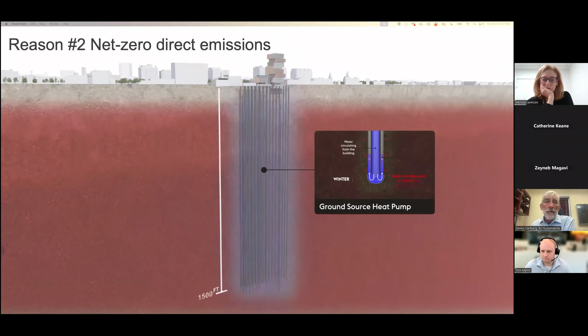The bore field has 31 closed-loop boreholes using water as the thermal transfer. These bores are connected to a plate and frame heat exchanger in the basement through 9 circuits. Water is used on the ground side of the plate and frame heat exchanger. A glycol water mix transfers the thermal energy from the other side of the plate and frame heat exchanger to the heat pumps, to allow those heat pumps to operate at colder temperatures below 32 degrees Fahrenheit.